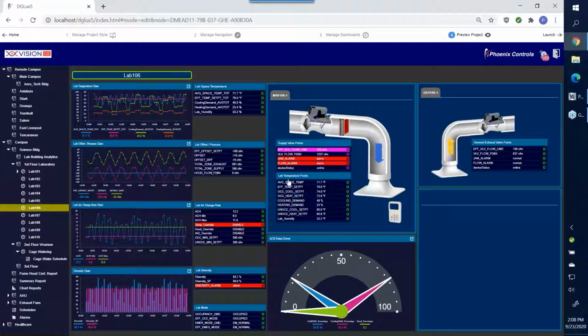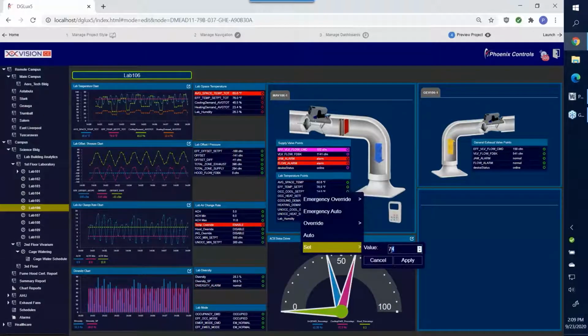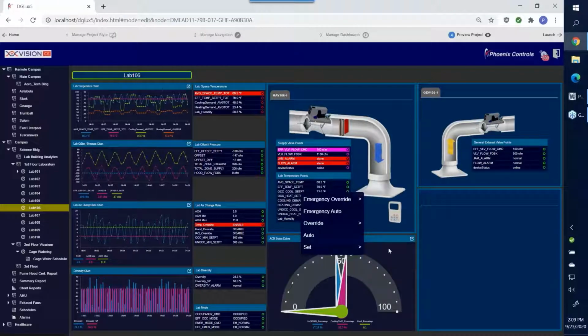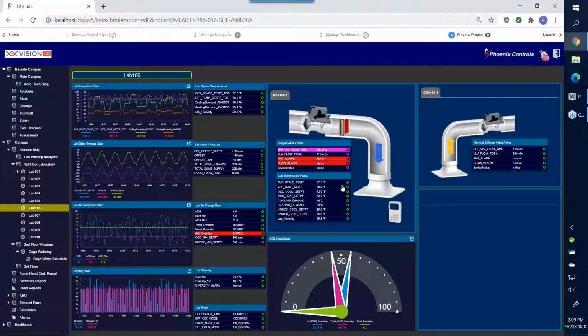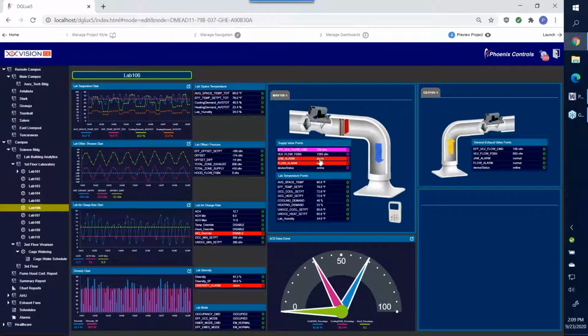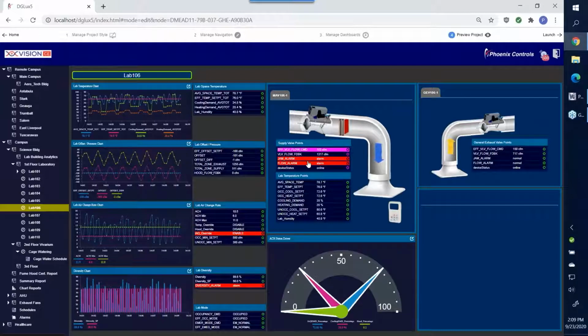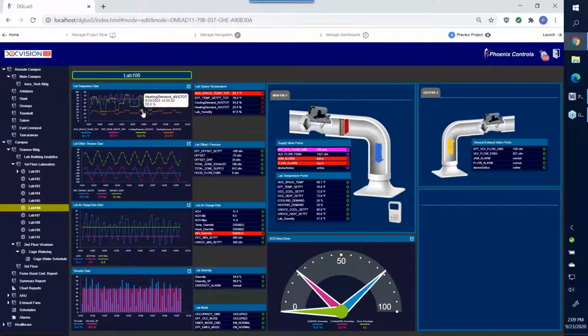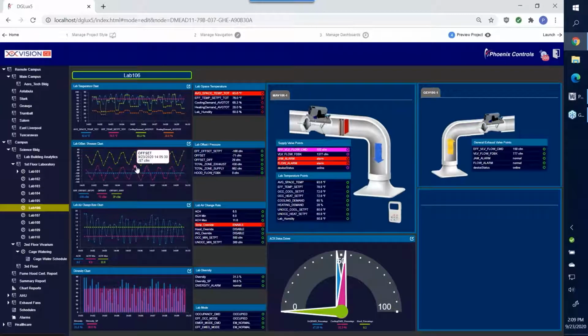If you make the points resettable, then you have all the functionality that you might with other systems, where you can change set points, you can come in and change any value that's made available as a set point very easily, either through a typical browser and or phone and or tablet. You have indication of overrides with the magenta bars, alarms within the points by the red bars, and again, a lot of capabilities from a standpoint of reporting and histories, because most of the time, you really don't want to wait until you have an event to then go back and set up a history or a trend. That's why we typically set up in these individual room modes at least 30 days of trend information, so that you always have some indication of what has occurred and gives you that troubleshooting and analytic capabilities.